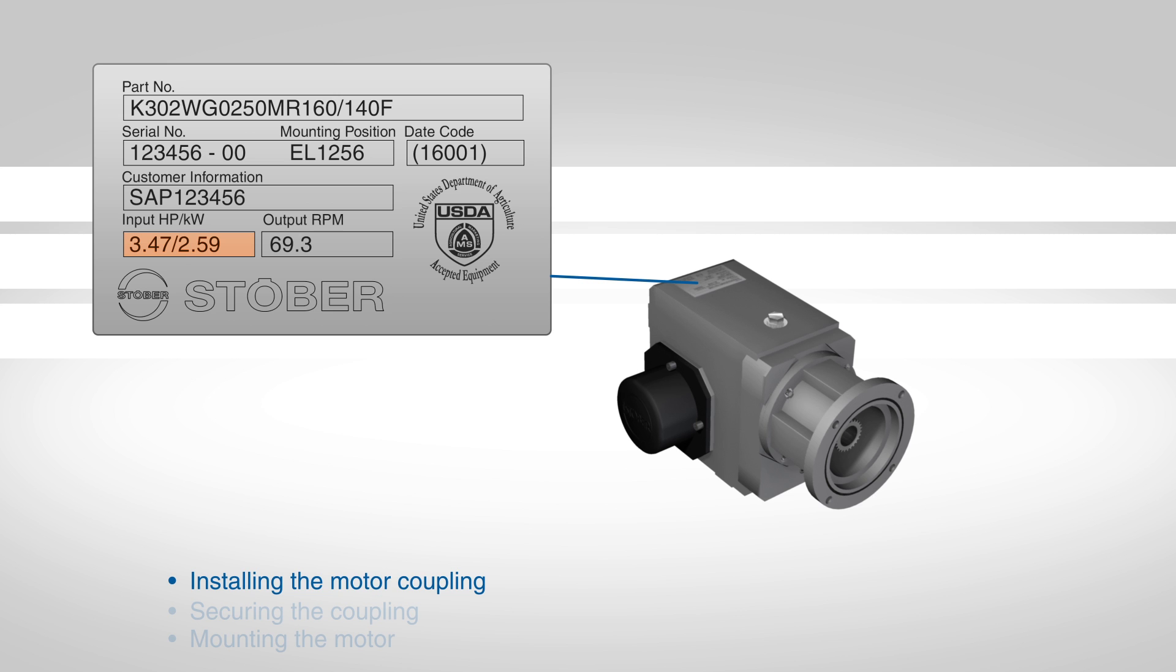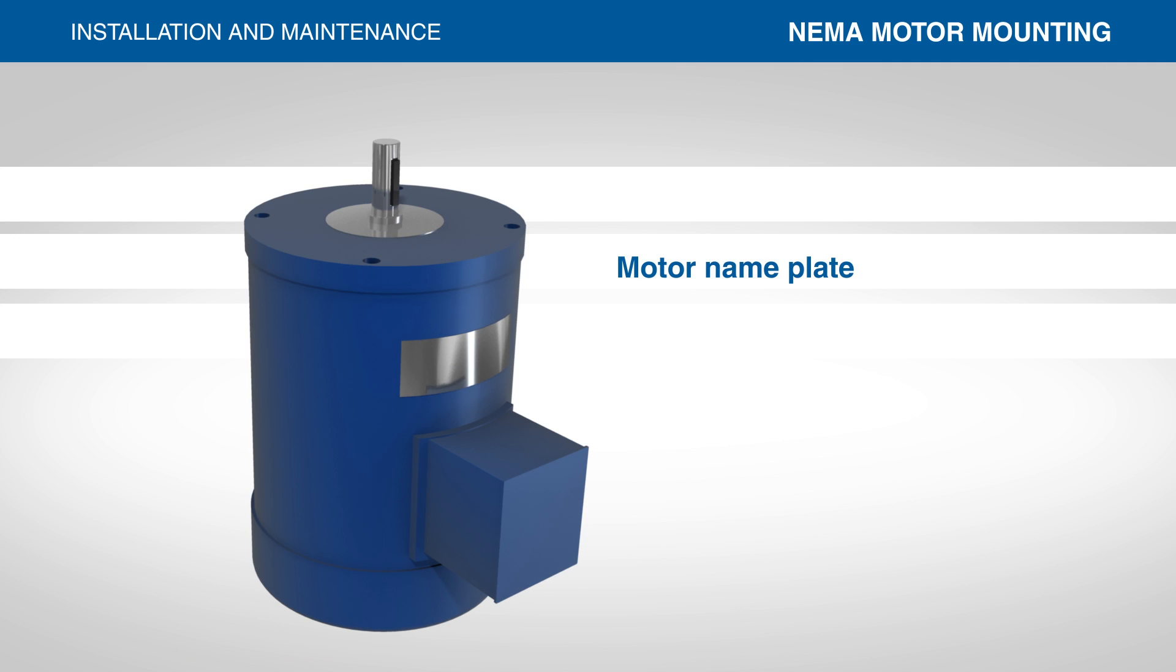The horsepower capacity is shown on the reducer's nameplate. Check the motor nameplate to make sure it is the correct horsepower, frame size, and speed for the reducer.